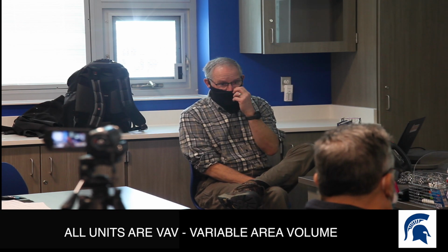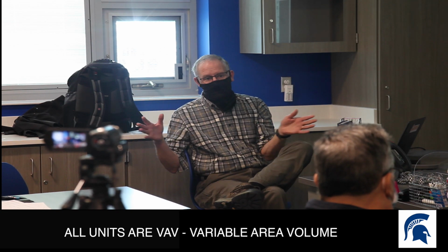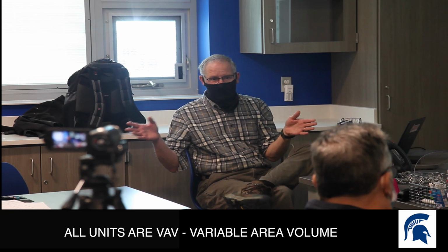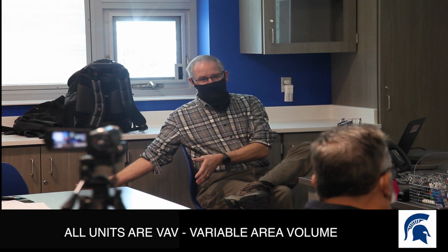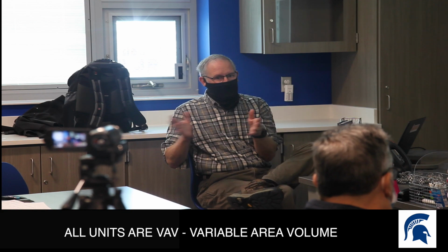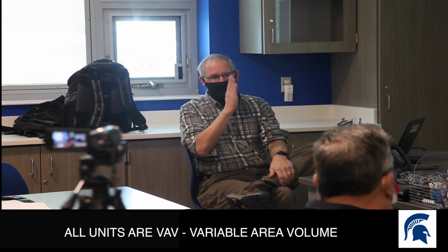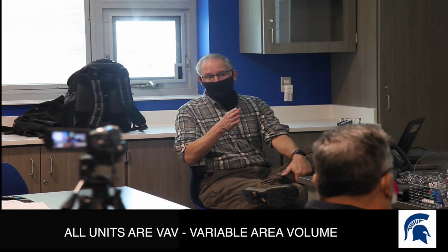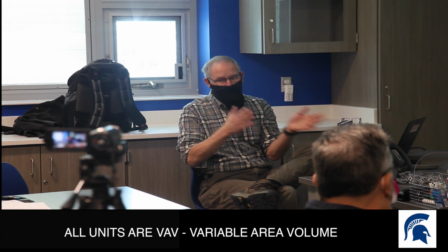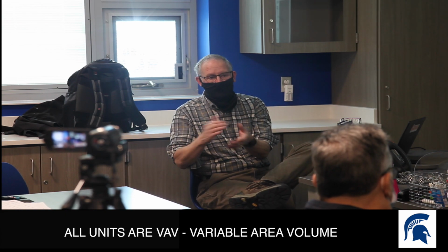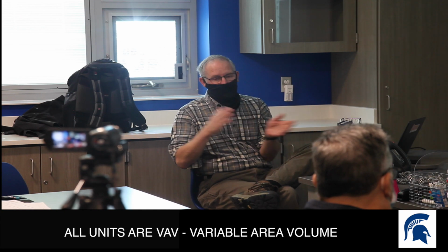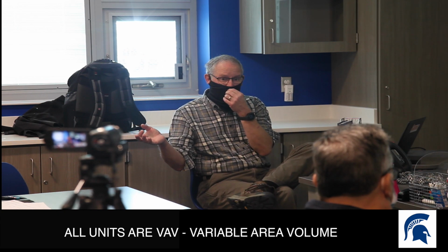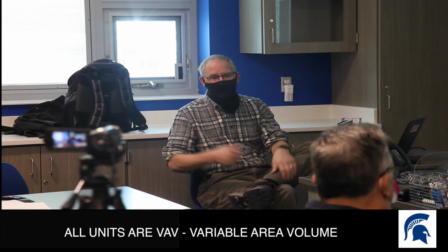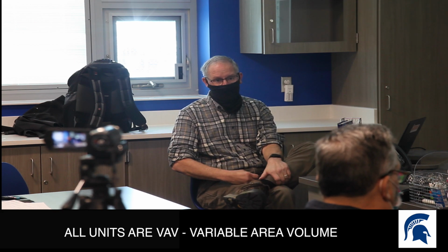Now, being that they're VAV, and you guys know what VAV is, it's variable air volume, it changes based on the need of the space, you're going to have to get the hang of that pressure drop if you're not going by a number per se, because the less air, the less pressure drop you're going to see across a set of filters. It's most critical when the machine's running at a pretty decent load. That's when you should see the larger pressure drops on dirty filters, okay?